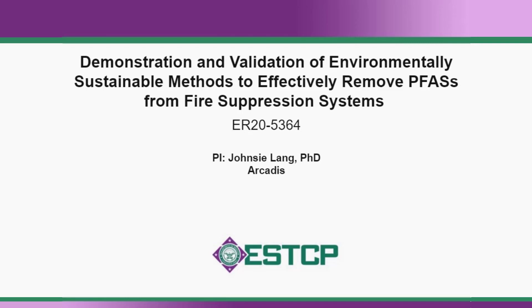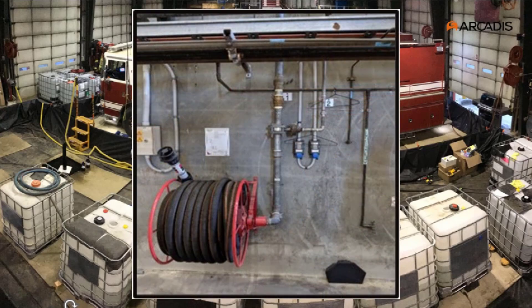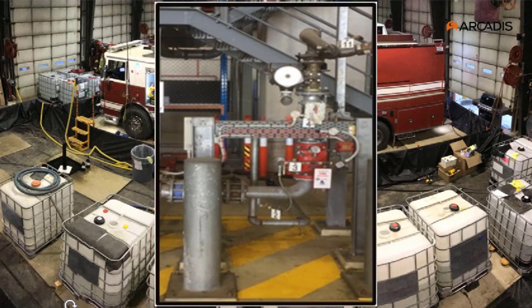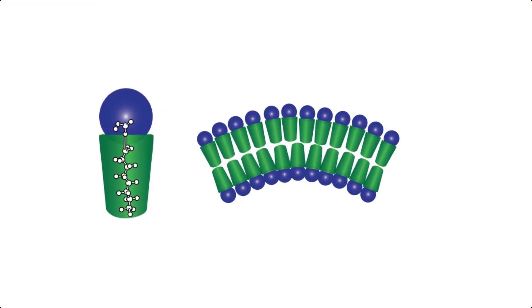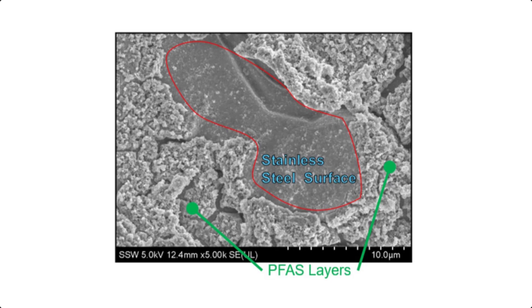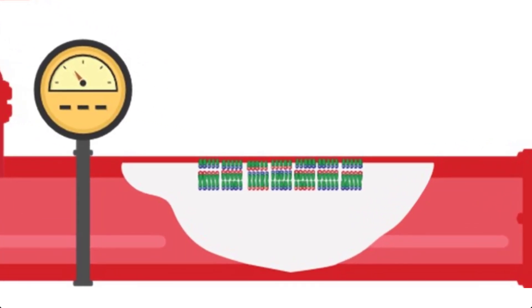Project ER20-5364. Fire suppression systems, such as hangar sprinkler systems and Aviation Rescue and Firefighting, or ARFF, vehicles, are impacted by residual PFAS adsorbed to internal surfaces as a result of the legacy and ongoing use of Class B firefighting foams containing fluorosurfactants, such as aqueous film-forming foam, or AFFF. When one firefighting formulation is replaced by another, new PFAS-free firefighting formulations can be impacted by residual, surface-bound PFAS within the fire suppression system.